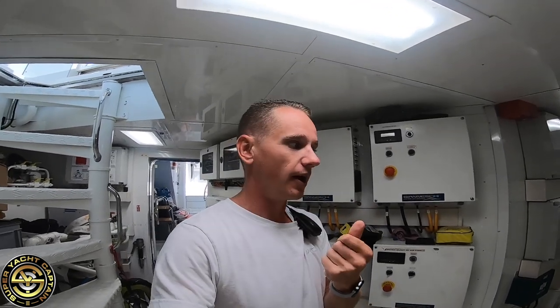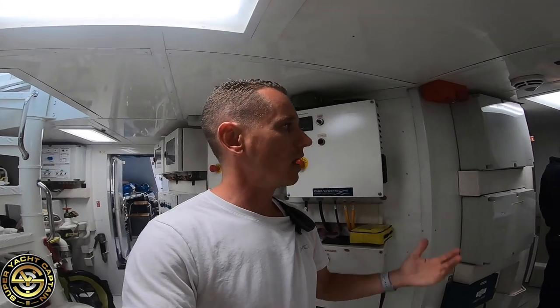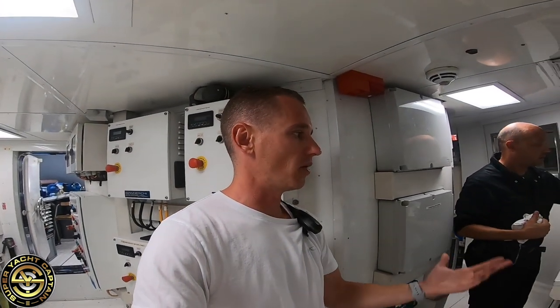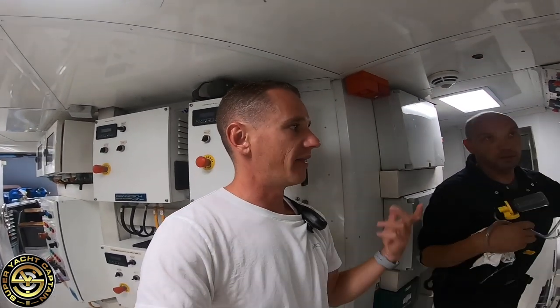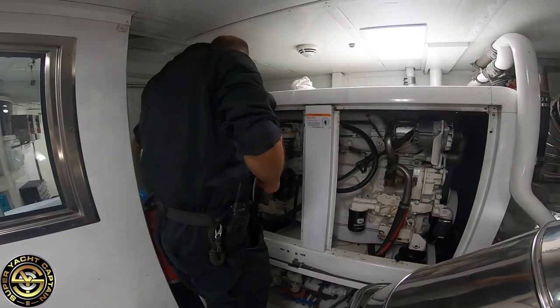What Slav is saying is: with the system we have on board, if we had a blackout on shore — if the electricity were to cut out — the generators would automatically come on and power up the boat. We don't want that to happen during the service, so he hits the emergency stop and turns off the main batteries for one generator at a time. He's now started the port side generator to heat up the oil, because warm oil is thinner and drains out much more easily.